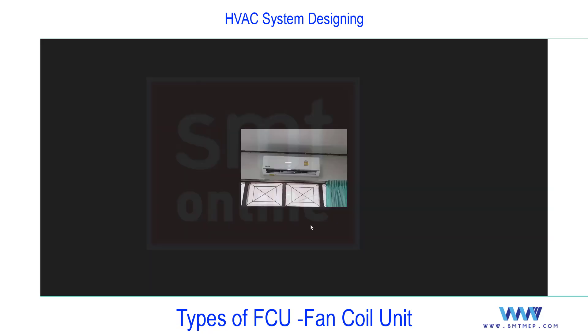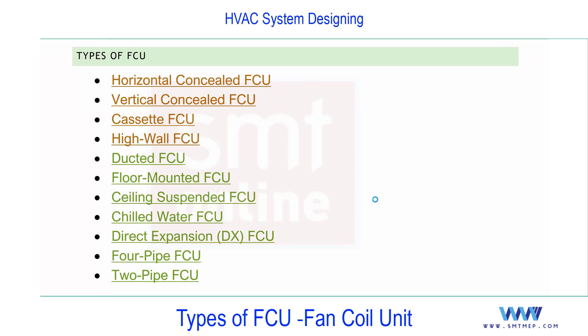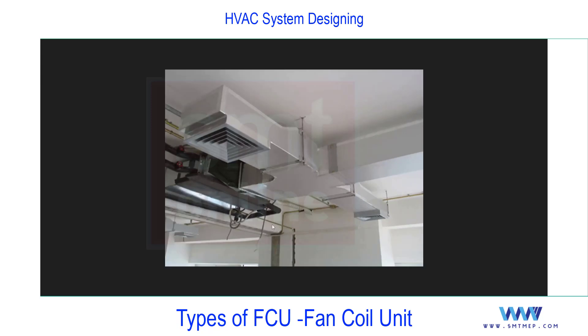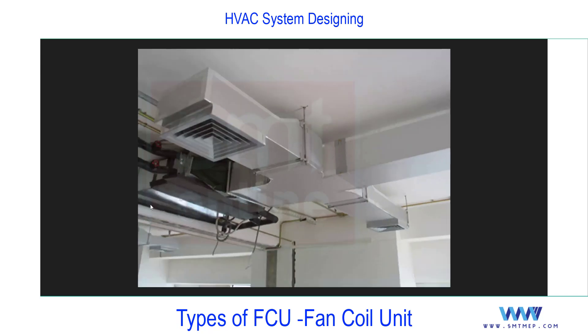Next is the cassette FCU and the high-wall FCU, both discussed previously in detail. Then there is the ducted FCU, where a duct is connected to the unit for more even air distribution within a single space — not for multiple spaces, since FCU capacity is limited. A canvas cloth flexible connector is used between the unit and the duct to reduce vibration transmission.